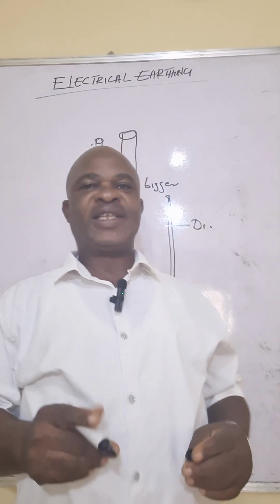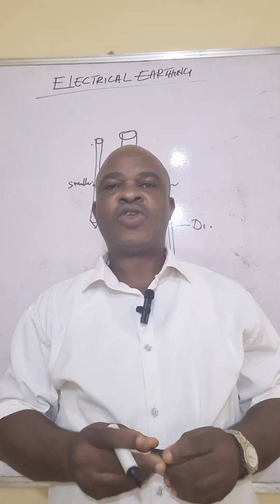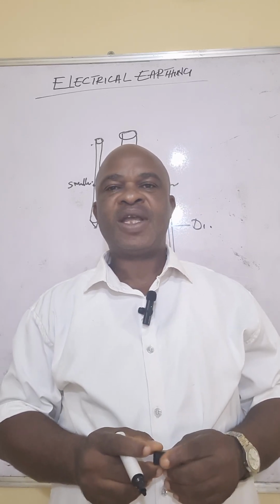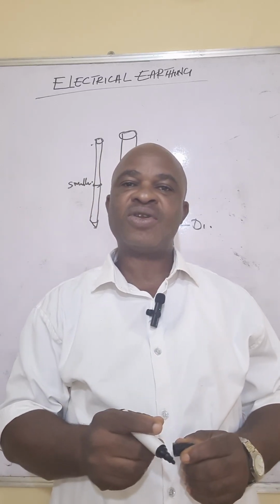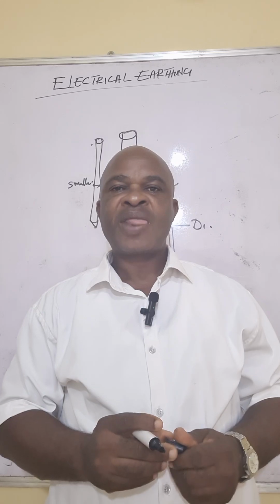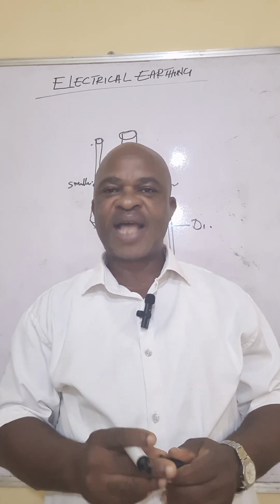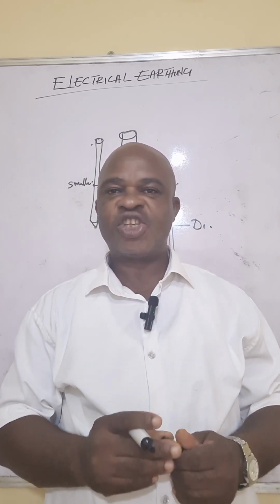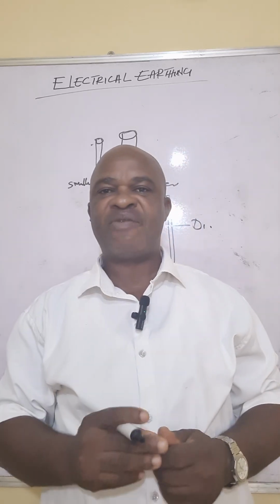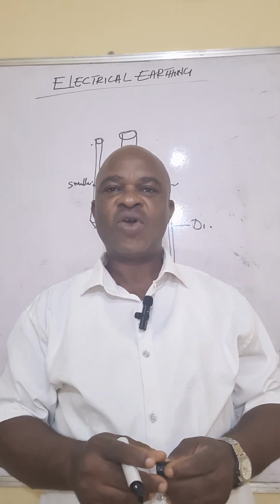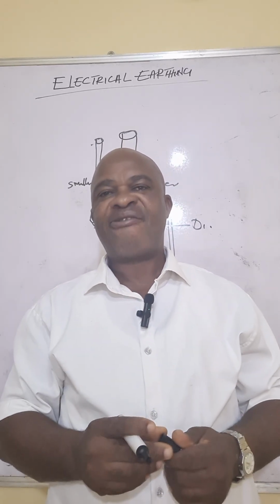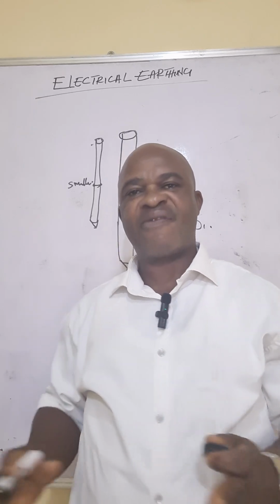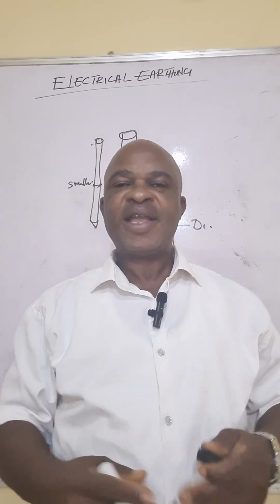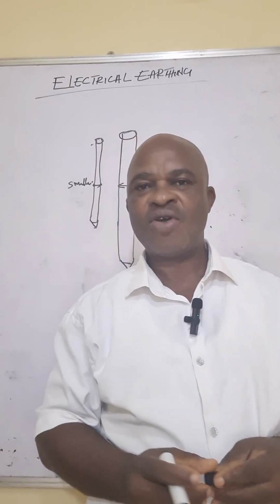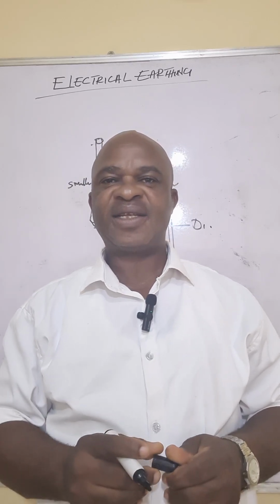Another thing we need to know is that the earthing resistance value should not be more than 2 ohm. This is what the regulation stipulates. But it depends on a number of factors. For example, if the area you want to earth is hilly or contains a lot of stones, the resistivity of that place is going to be very high. So there is no way you can get 2 ohm or below. Therefore, the regulation says that for this kind of place, between 2 and 10 ohm is okay. So this is the value you can arrive at to prove that the earthing process you are doing is okay.